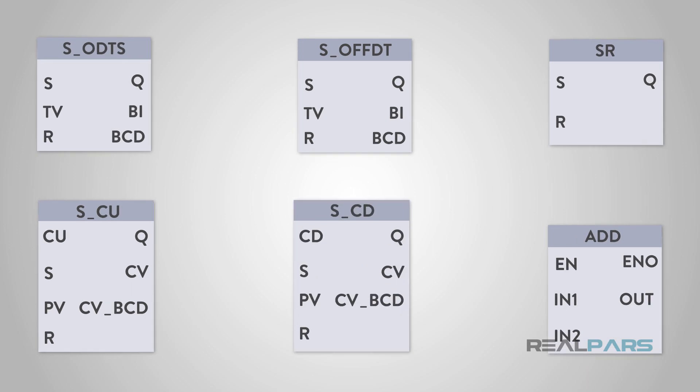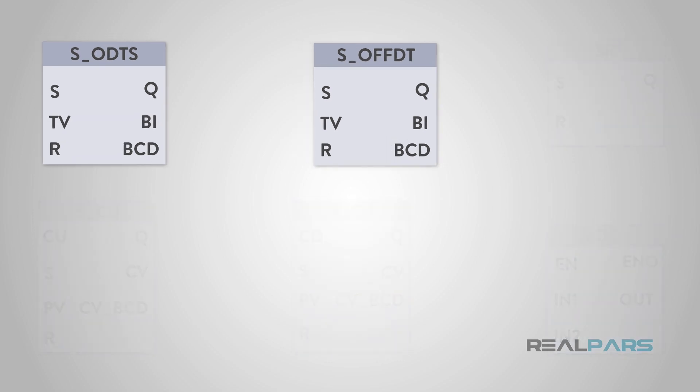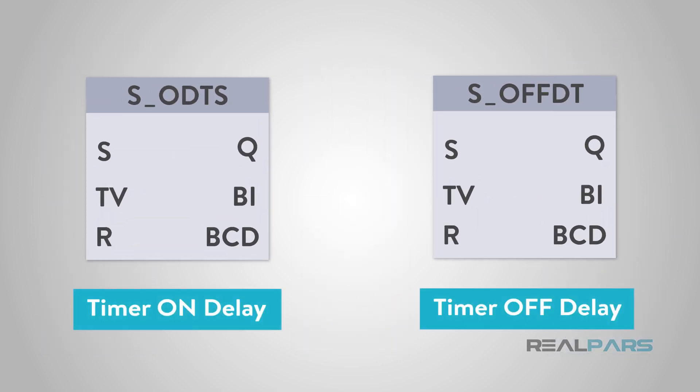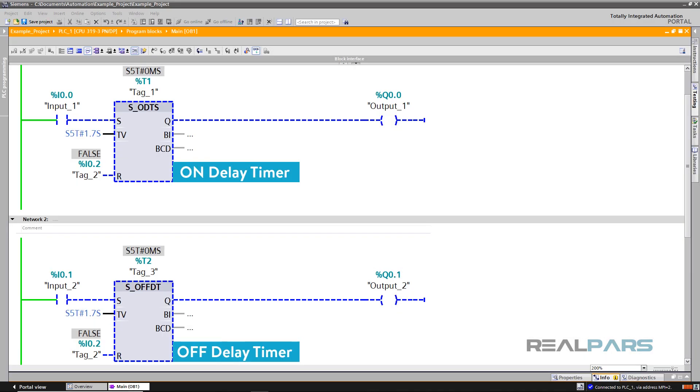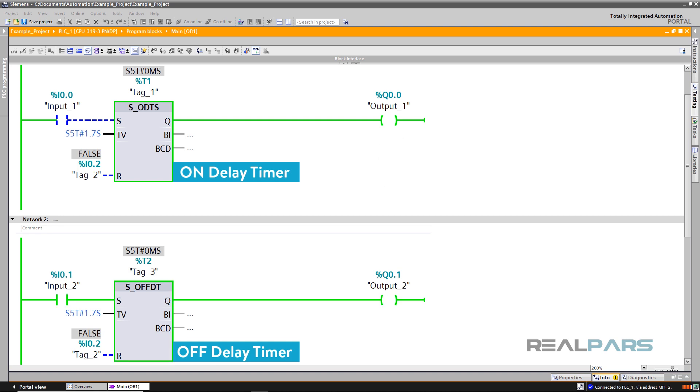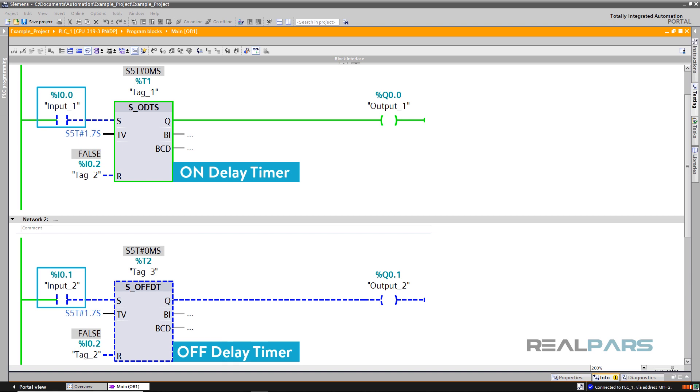Probably the most common is a timer. More specifically, the two basic types: the timer on delay and the timer off delay. A timer on delay will wait to turn an output on after the set period of time. A timer off delay will turn the output off after the set period of time. Both timers must be triggered by an input. Once the input is energized, the timer will start.